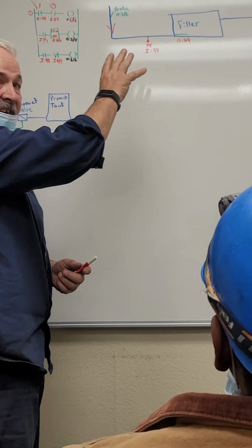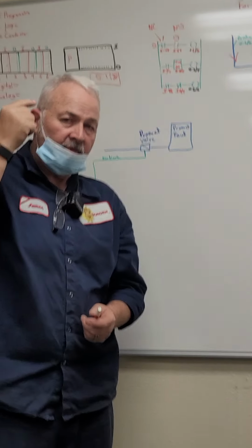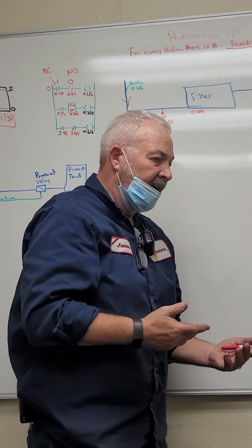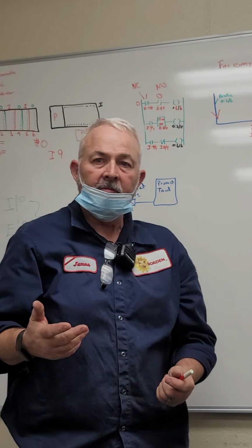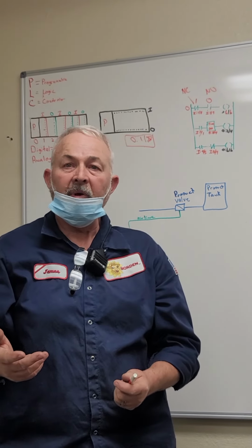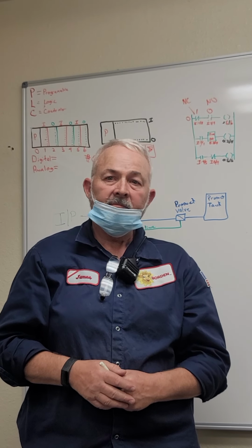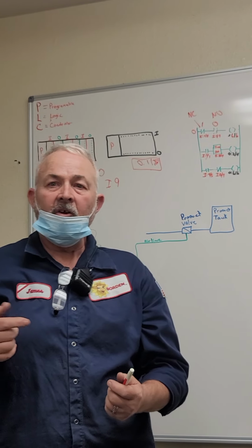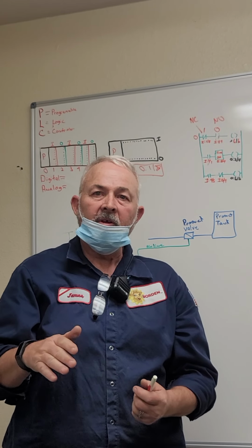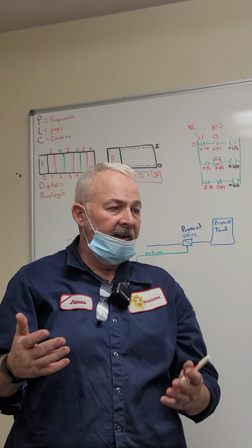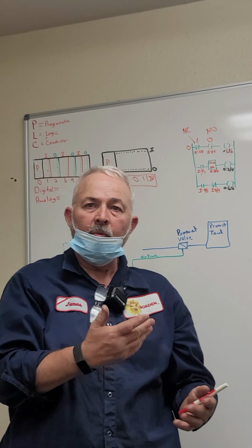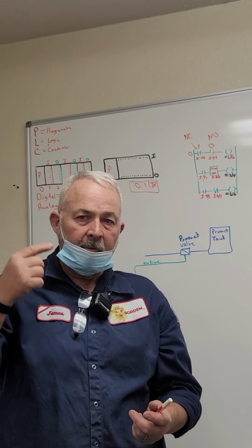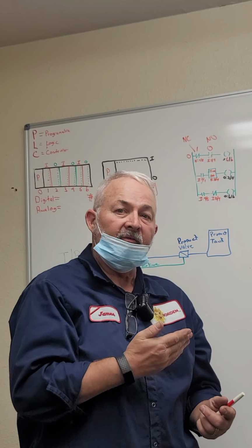The fact that y'all are learning this should make y'all start thinking about when you get called out to the N8, and let's say the in-feed line, the side tube belt won't turn on. Or let's do even better than that: let's say that it won't feed cartons. Your work plate won't pick cartons. Lines 2, 3, and 4 are running, but line 1 will not pick a carton. It should make you start thinking about what will keep line 1 from coming on.